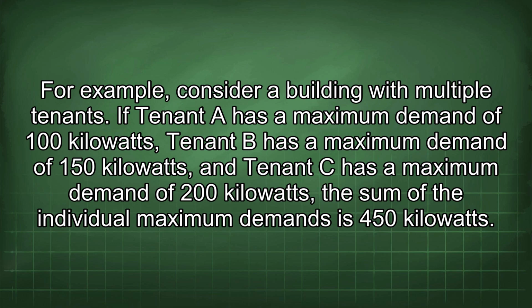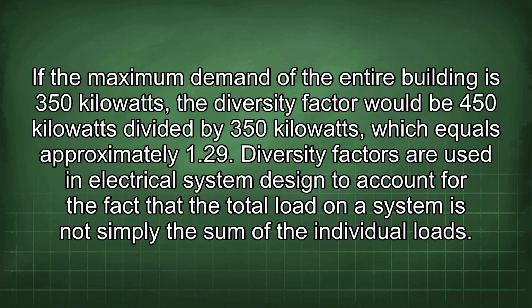If tenant A has a maximum demand of 100 kilowatts, tenant B has a maximum demand of 150 kilowatts, and tenant C has a maximum demand of 200 kilowatts, the sum of the individual maximum demands is 450 kilowatts. If the maximum demand of the entire building is 350 kilowatts, the diversity factor would be 450 kilowatts divided by 350 kilowatts, which equals approximately 1.29.